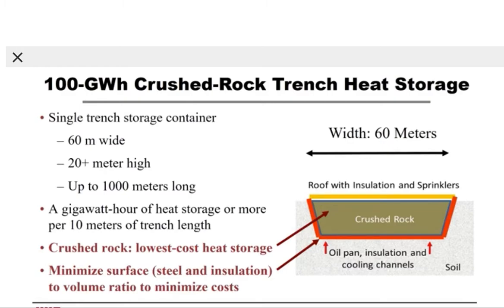The next slide shows the 100 gigawatt hour crushed rock trench storage system — a single trench storage container filled with crushed rock with a width of approximately 60 meters, a height of 20 meters, and up to 1,000 meters long. That yields a gigawatt hour of heat storage or more per 10 meters of trench. Two important design features: the trench is filled with crushed rock, the lowest cost heat storage material, and we have minimized the surface to volume ratio, thus minimizing the amount of steel insulation needed.